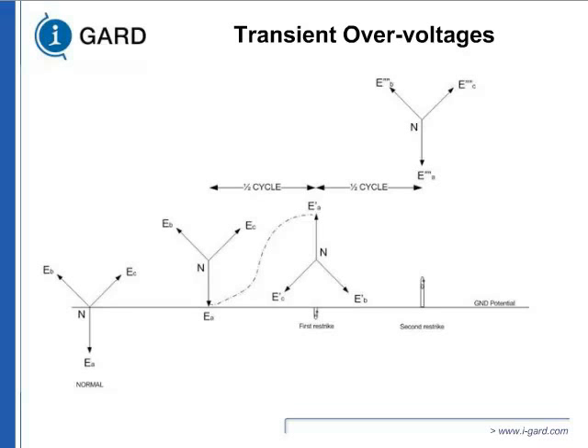Every half cycle, since the arcing is going on, the capacitance restrikes. After half a cycle, you see the neutral elevates even further. This will keep on going till something fails. Normally, some insulation, either cable or somewhere, will fail at 6 to 8 times and the system will shut down. But if it does not fail, it can ignite.